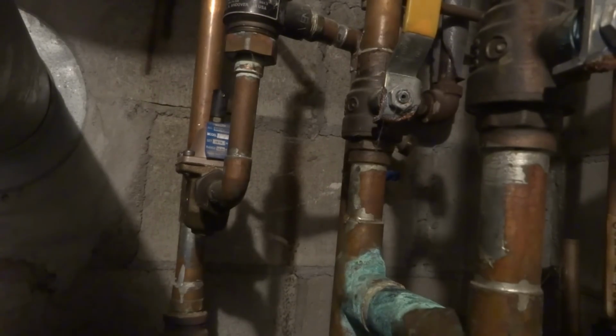Yeah, so seeing your repeat customer, I won't say anything about the mice. That's very good. Cleaned burners, clean burner tubes, ran boiler, fired up nicely. Alright, well that should take care of it.